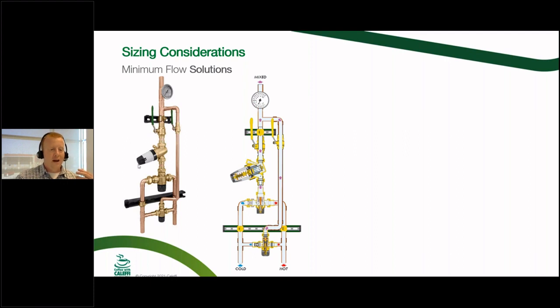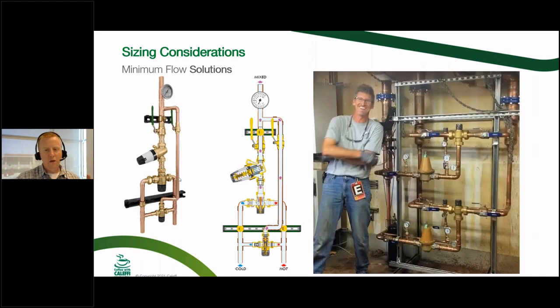So you want to have this valve start opening up at just the perfect time, like when this valve here is starting to reach about 8 or 9 gallons per minute. Then this pressure reducing valve is going to open up and start taking that big guy in there and letting it go the rest of the way up to that 50 gallons per minute. So you can even field assemble these high-low assemblies as well. Just something to bring up.